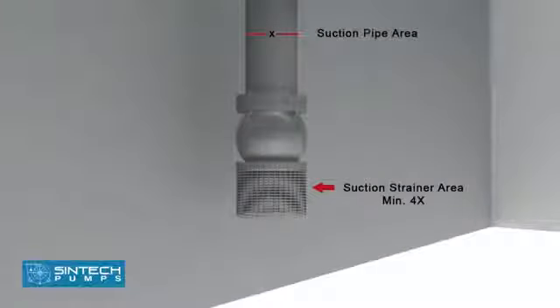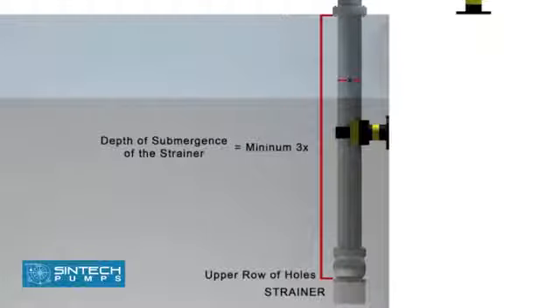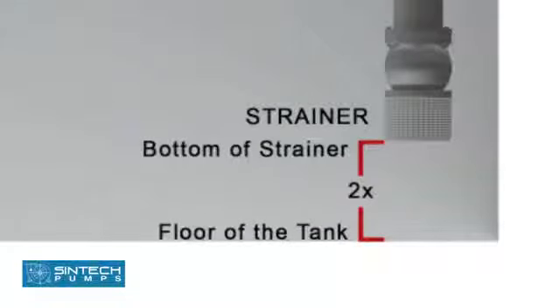The suction strainer must be at least 4 times the suction pipe area, and the mesh size should screen out solid particles that could clog the impeller. The minimum depth of submergence of the strainer should be at least 3 times the pipe diameter, measured from the upper row of holes of the strainer. The distance between the bottom of strainer and floor of the tank should be 2 times the pipe diameter.